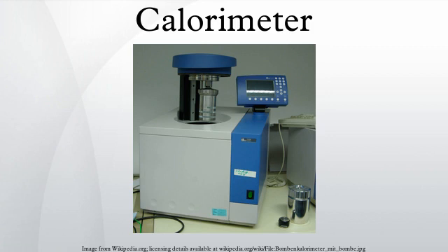The weighted reactant put inside the steel container is then ignited. Energy is released by the combustion and heat flow crosses the stainless steel wall, thus raising the temperature of the steel bomb, its contents, and the surrounding water jacket. The temperature change in the water is then accurately measured with a thermometer. This reading, along with a bomb factor, is used to calculate the energy given out by the sample burn.